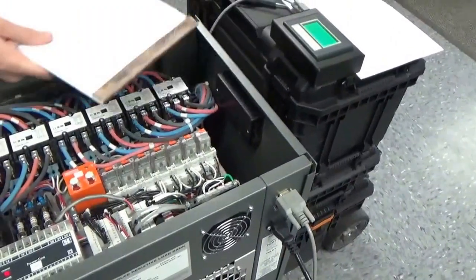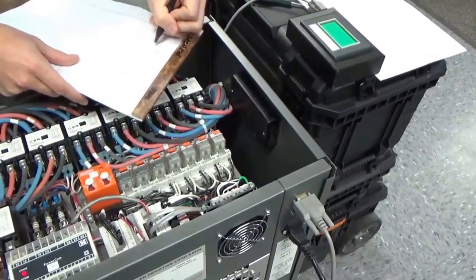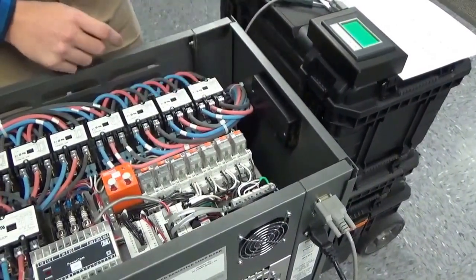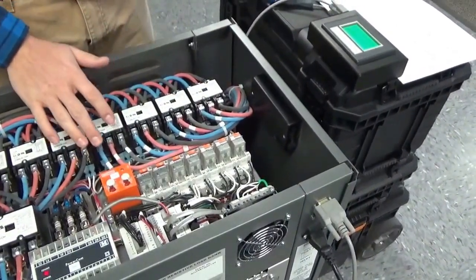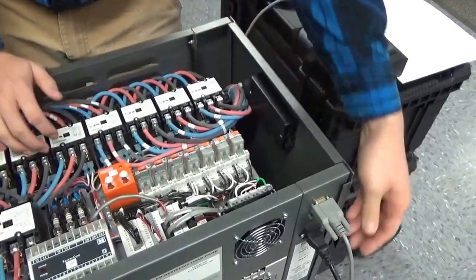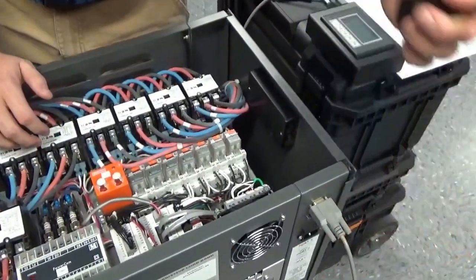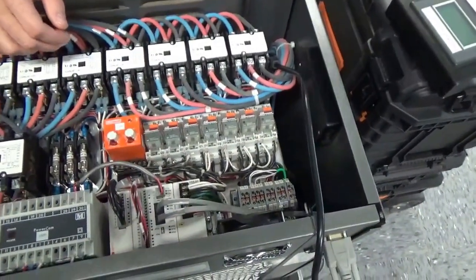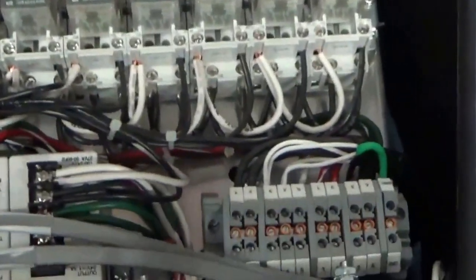What I'm going to do, I'm going to write down that number, 0.36. Now, that's going to be our current with four fans. So what we're going to do from here is remove control power and we're going to remove one of the fans from the control power circuit.